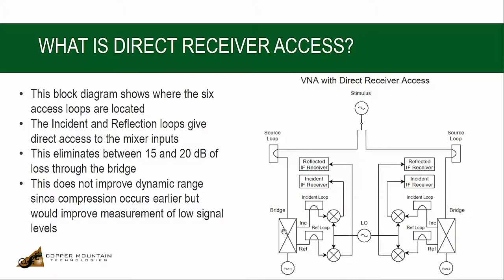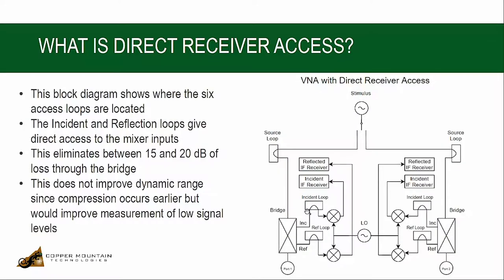The measurement bridge separates incident from reflected signals, and so the incident, the measured incident, or coupled incident signal from the bridge, then is available on the incident loop, which is called Ref 1 here. The reflected signal is available on the reflection loop, which is called Meas 1 here on the front panel.